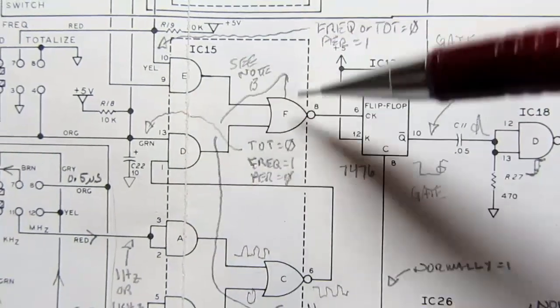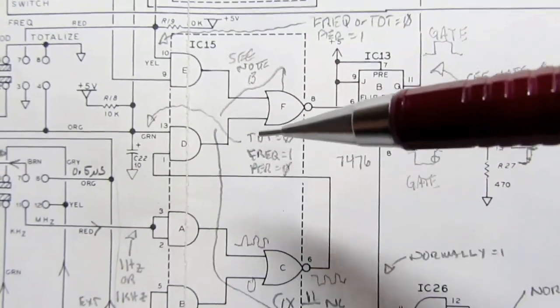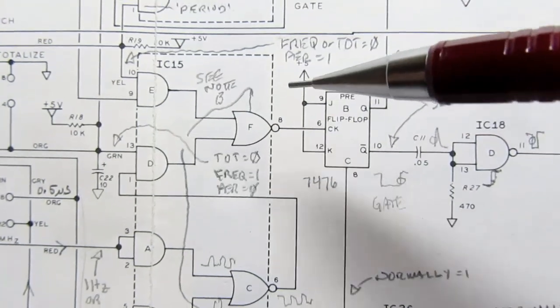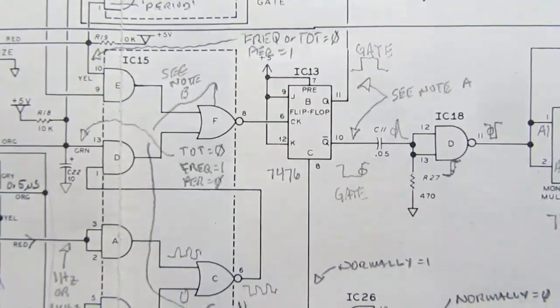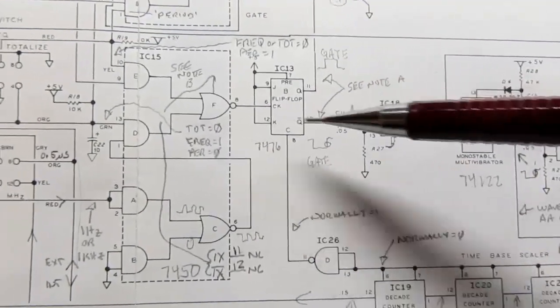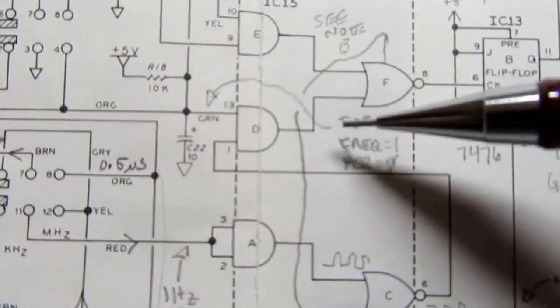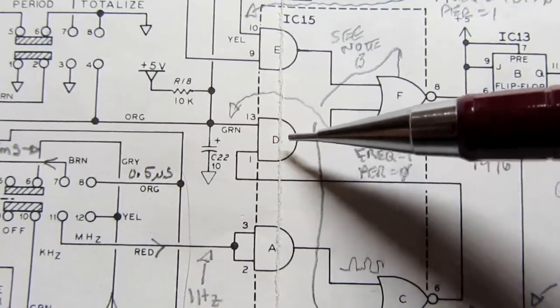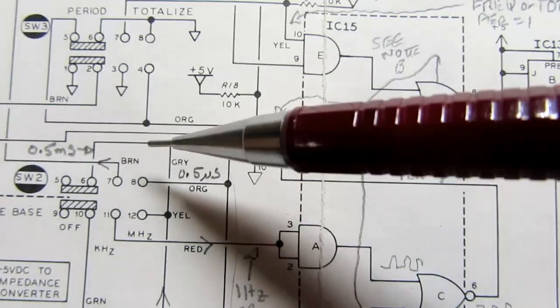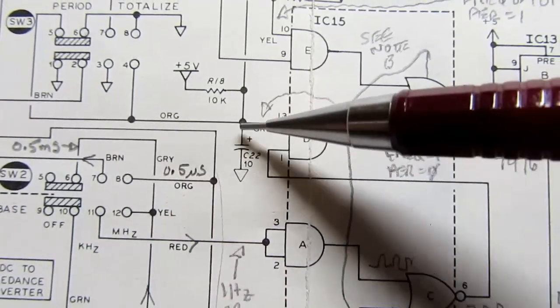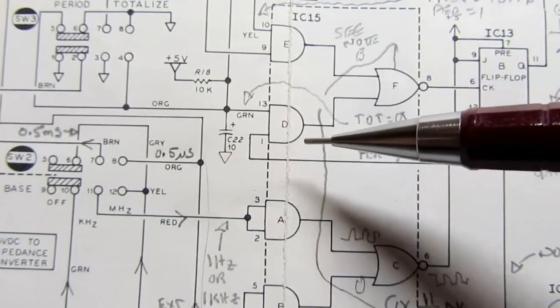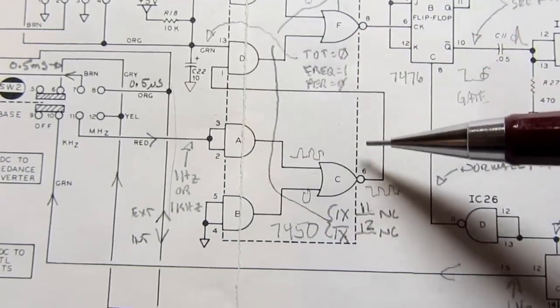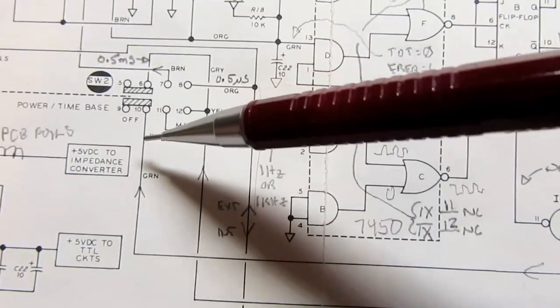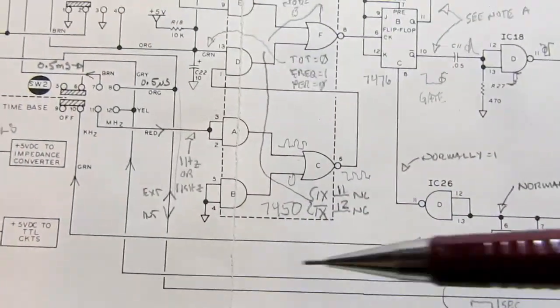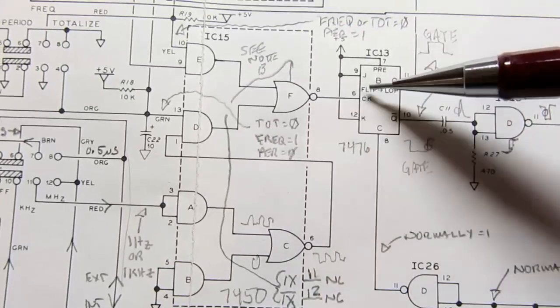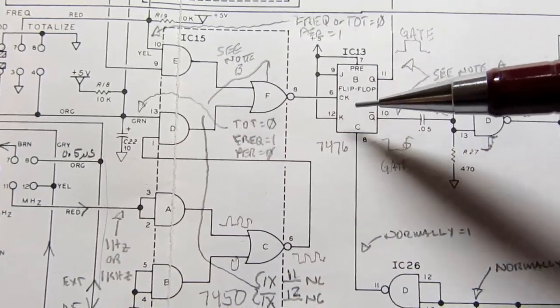That wraps back into an OR gate, and this here is used combinationally to select which signal source goes into this flip-flop. So normally the logic coming off of here is associated with the gate. This gate down here is enabled when the function selector switch on the front panel is in the frequency counter mode, thereby allowing the signal coming from the master clock—selected as kilohertz or megahertz—to pass through and go to this flip-flop, generating the gate signal.